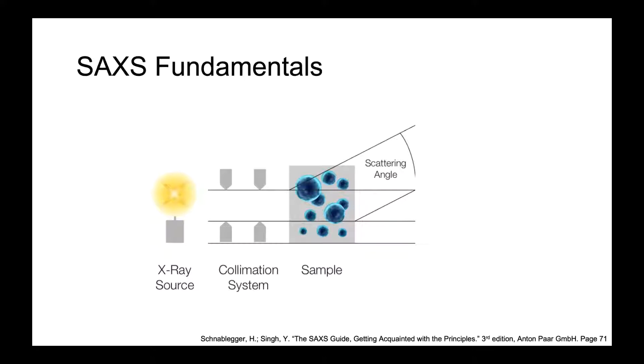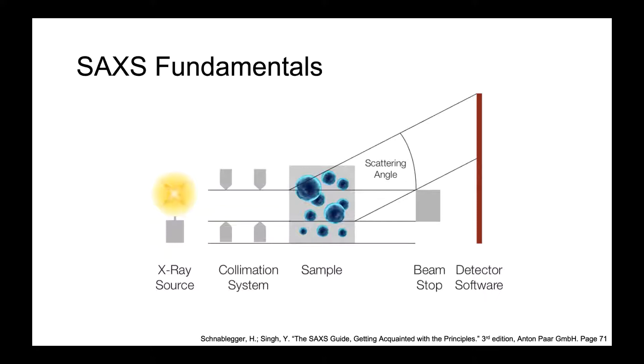As those x-rays make their way to the detector, they pass by a beam stop, which serves two major functions. First, it blocks out the direct beam, making it much easier to detect the scattered x-rays you want to look for. Second, it protects your detector from the direct beam so it doesn't get oversaturated, helping with both getting the measurement and prolonging the life of the instrument. Finally, those scattered x-rays make their way to the detector.